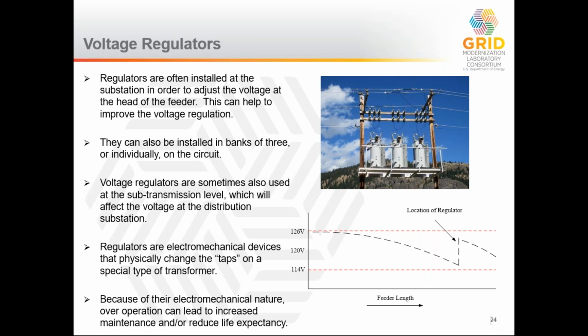Here's another example of putting a regulator further out from the substation, because sometimes even if you move the voltage at the head of the feeder to the top end, you still may violate the low end by the end of the circuit. In this case, we see an example of a voltage regulator put out toward the end of the feeder, where the voltage drops down, then it taps back up, and then it starts to drop again. In this way, you can put multiple regulators on there to extend the length of a circuit. This allows you to go further, and it provides a higher level of regulation.